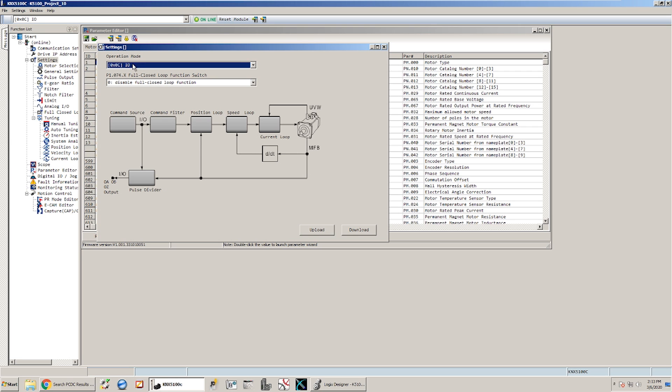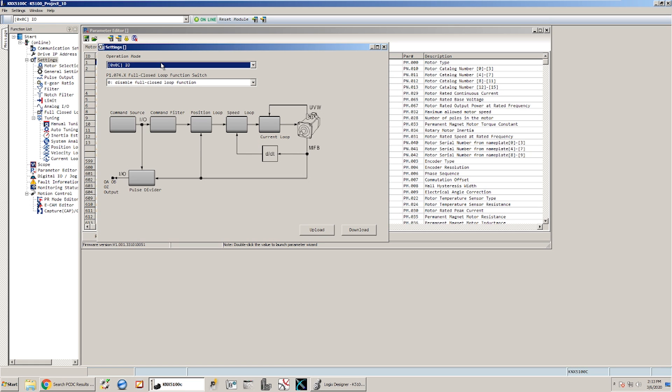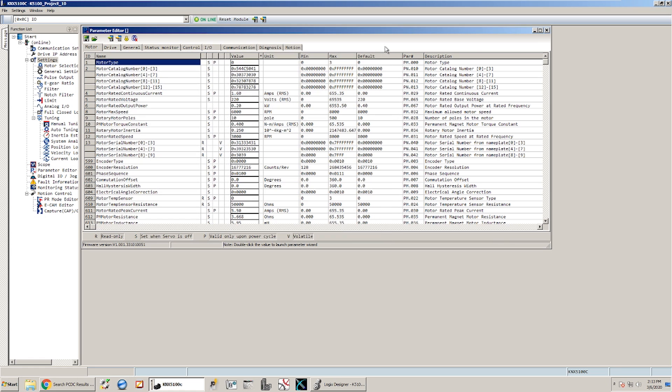And the second thing that we need to have is we need to have the mode setting correct for the drive. To do the add-on instructions we want the operation mode set to I.O. So if you're doing pulse and direction or following a velocity signal you would set that up here, but in this case we want it set to I.O. so we can use the add-on instructions.